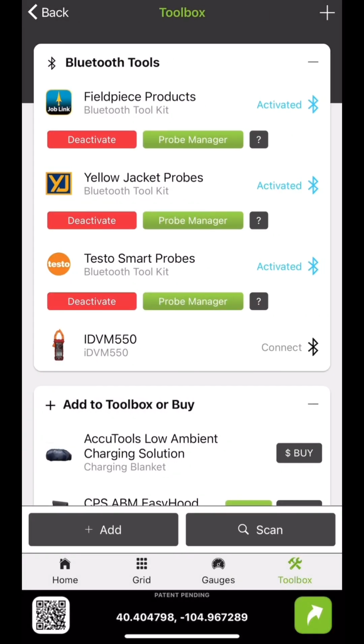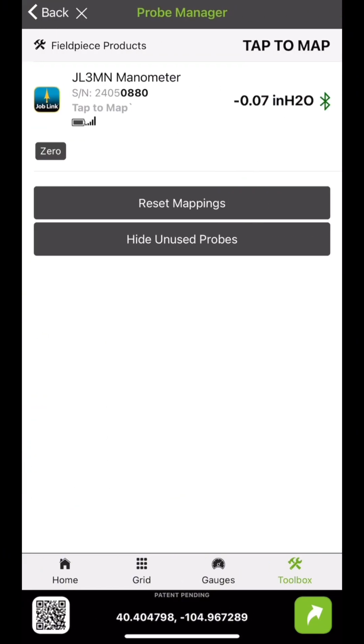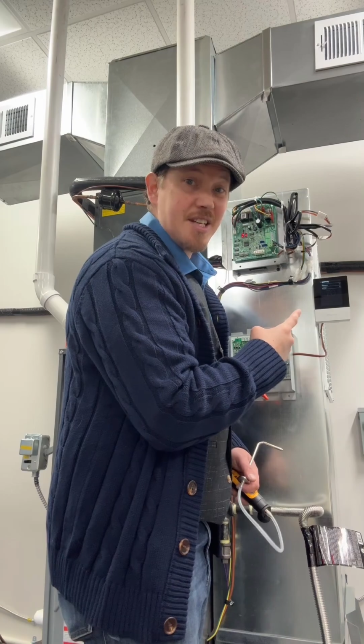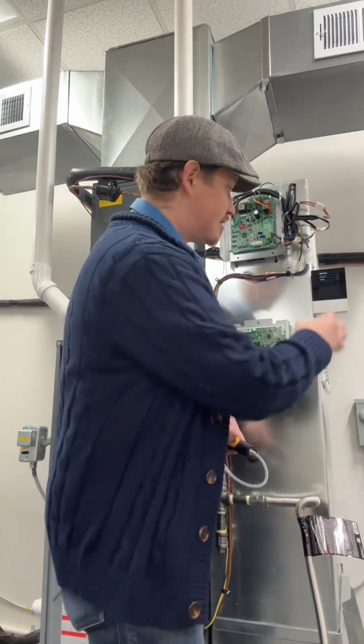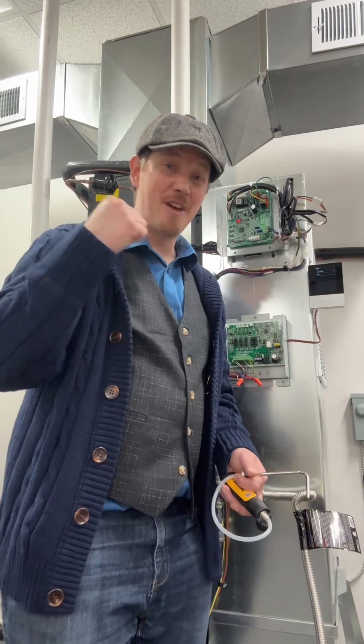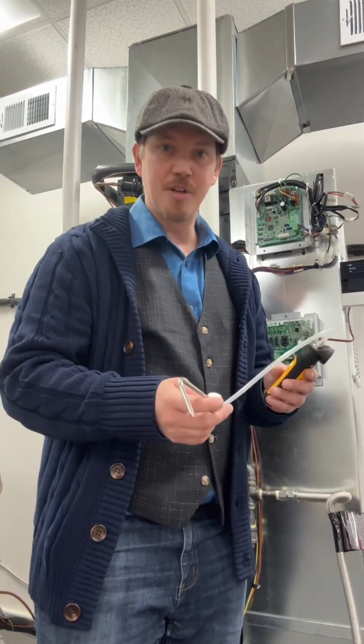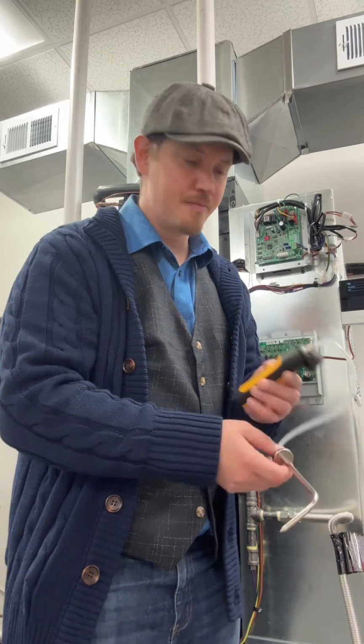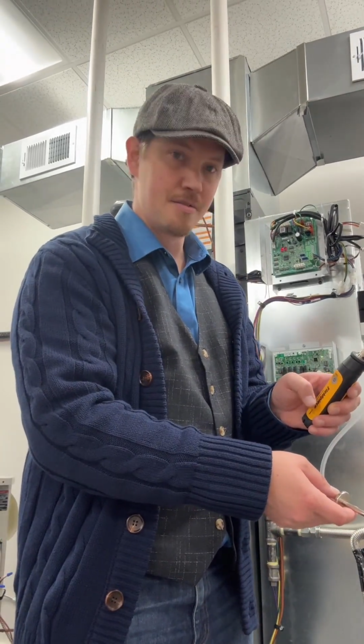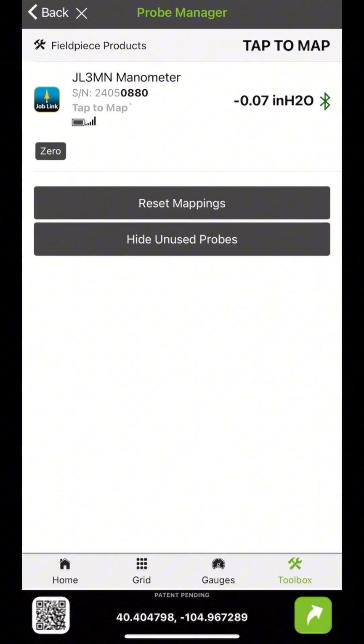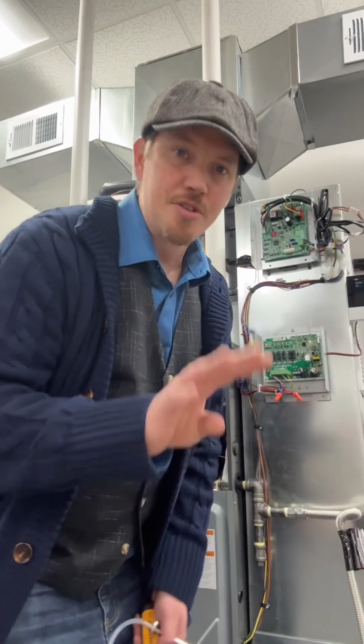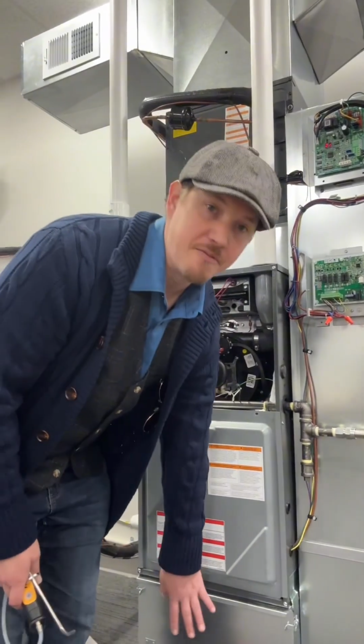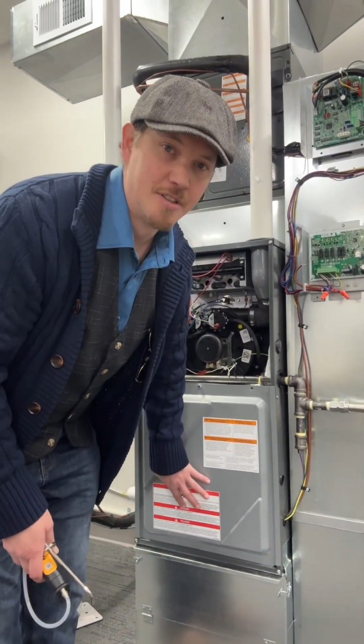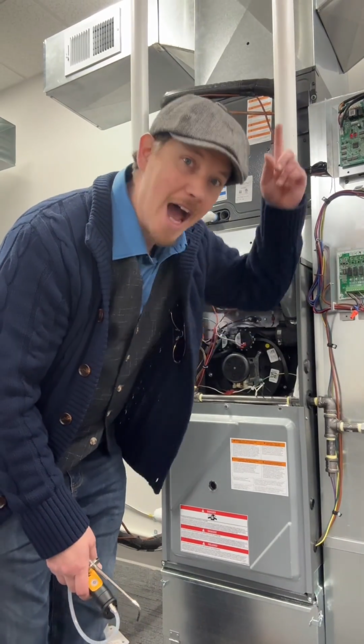At this point, you're gonna open up measureQuick and make sure that your tools are selected. You need to tell the system to run the fan at the highest fan speed. So once this system tells my fan to start running, I can start my tests. I'm gonna turn on my probe. Boop. I'm gonna make sure it's zeroed. Once you zero out your tool on the tool, you'll notice in the toolbox it goes to 0. So there are 4 places to take static pressure. We have before the filter, after the filter, before the coil, and after the coil.